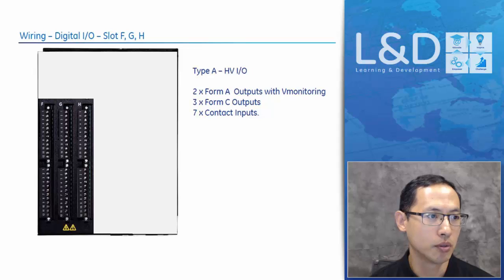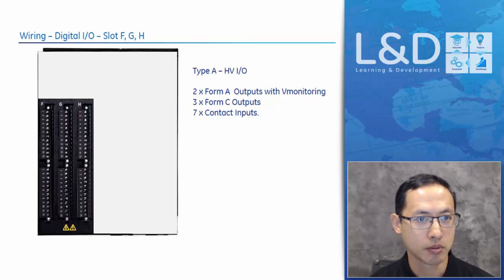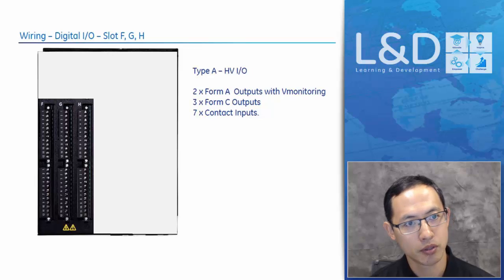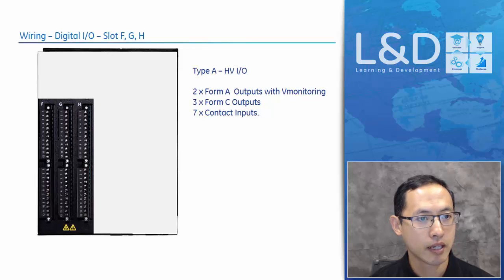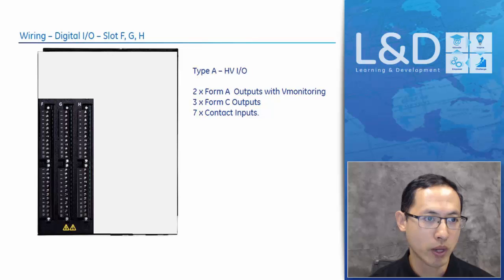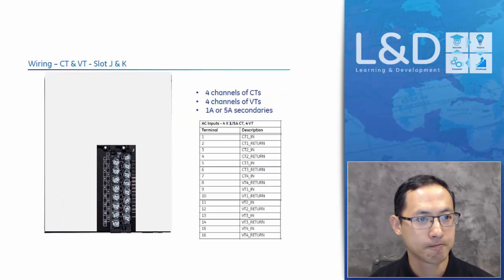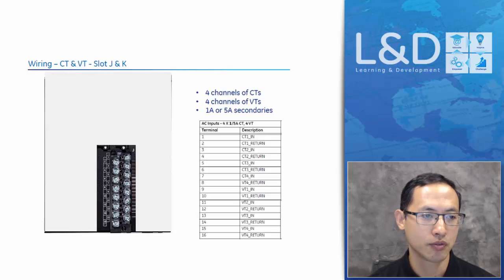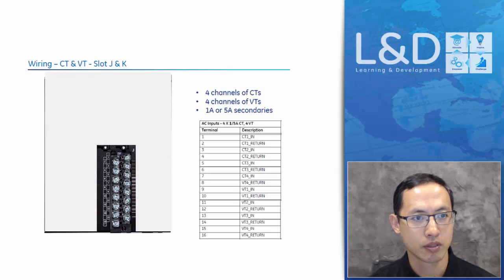The high voltage I/O has the output relays and input contacts. For the output relays, it has 2 form A and 3 form C output relays. The form A has voltage monitoring, which can be used to monitor the trip coil and close coil, and the contact inputs can be set to dry and wet mode. And for the analog inputs, or CT/VT inputs, we have a standard J slot for the feeder relays, or the optional K slot for the sensitive ground for the 850, and also for the 869 and 845. The second slot can be used for differential relay inputs.